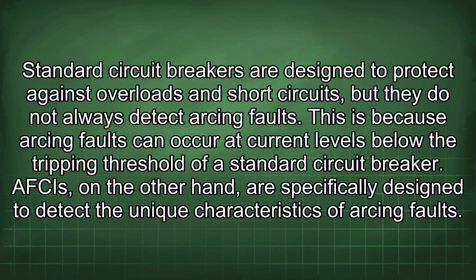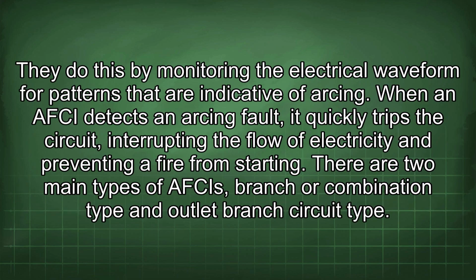AFCIs, on the other hand, are specifically designed to detect the unique characteristics of arcing faults. They do this by monitoring the electrical waveform for patterns that are indicative of arcing. When an AFCI detects an arcing fault, it quickly trips the circuit, interrupting the flow of electricity and preventing a fire from starting. There are 2 main types of AFCIs: branch or combination type and outlet branch circuit type.